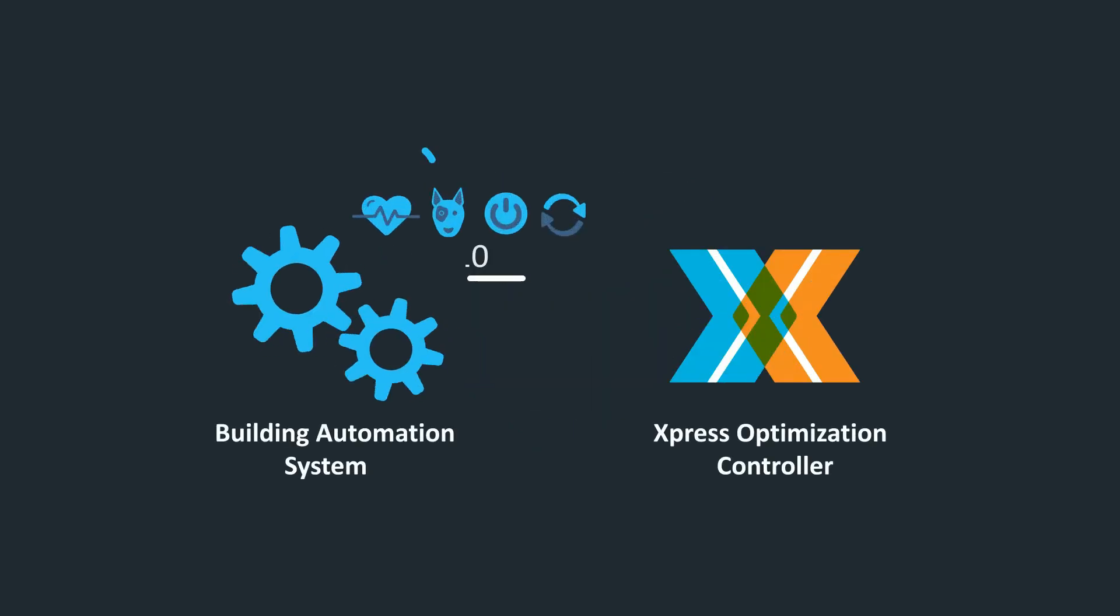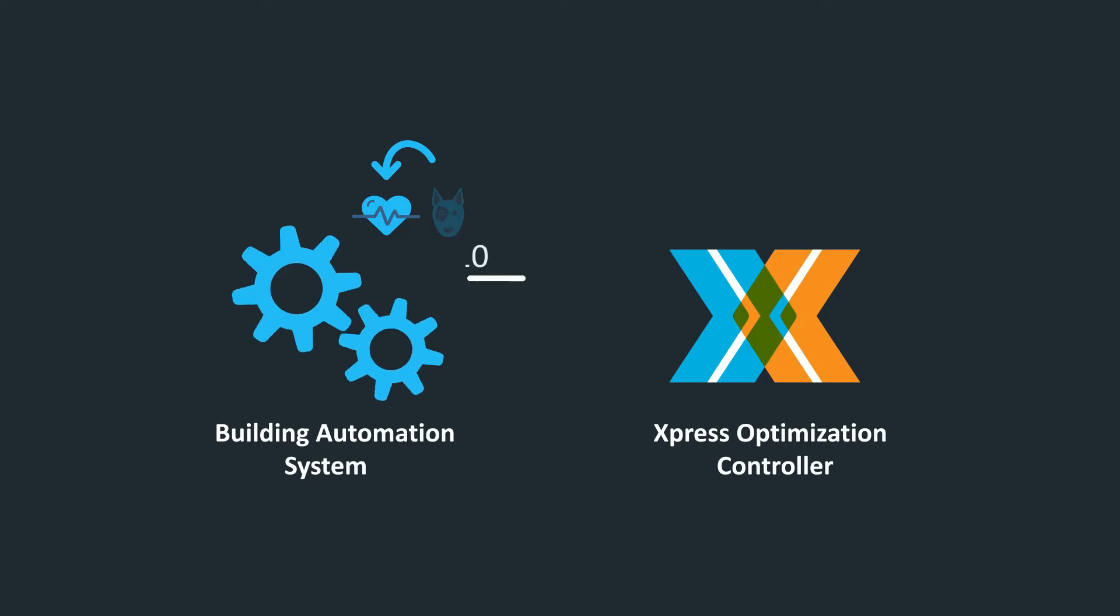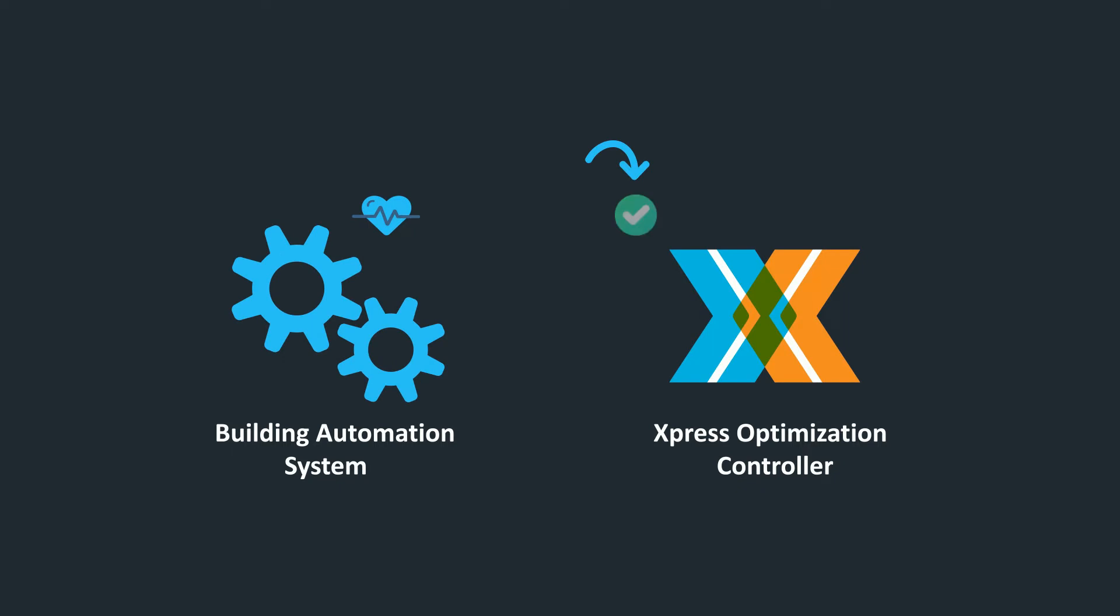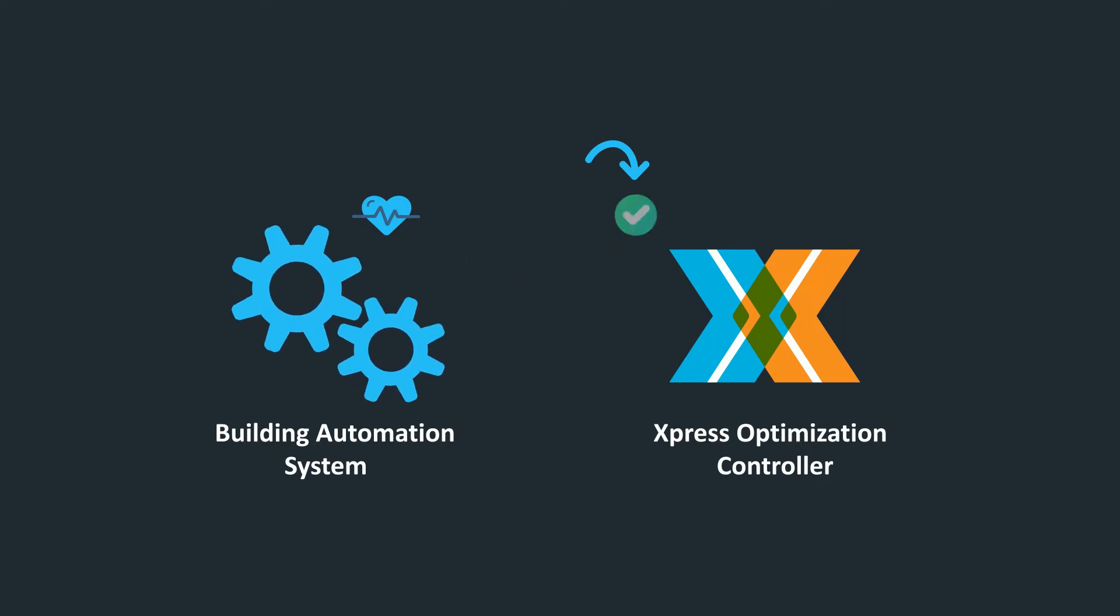The System Heartbeat is one of two components that establish the communication monitoring protocol between your building automation system and the Express Optimization Controller. The Heartbeat program you create using this video will allow the Express Optimization Controller to determine whether or not the data being received by your BAS is stale.